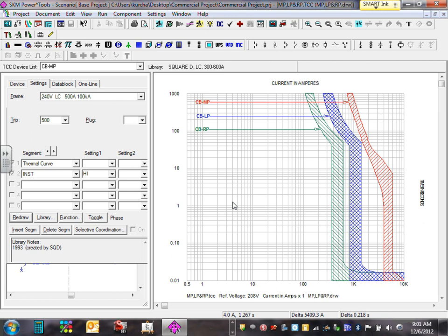Before I leave here, very good point, Kerry, can everybody understand that if the curves are not touching, they are fully coordinated? The only time they're not coordinated is right in here, right at this corner. And you know what this is? This is where all hell breaks loose.